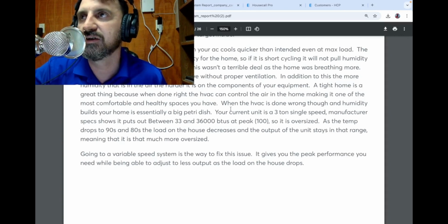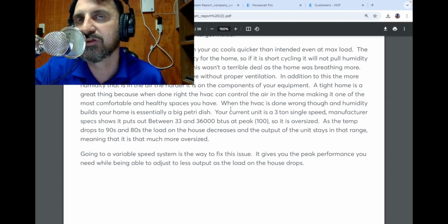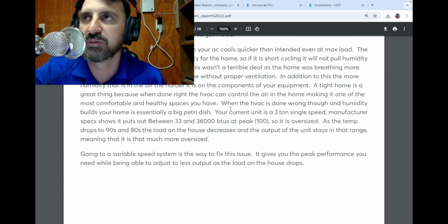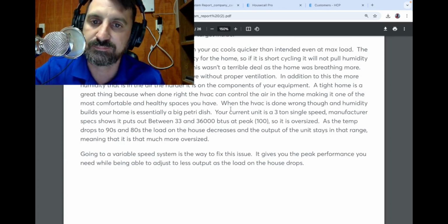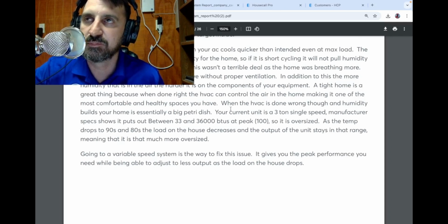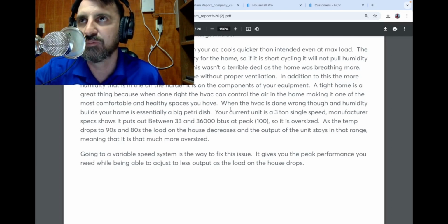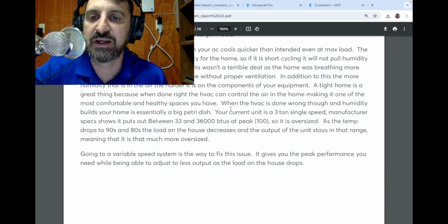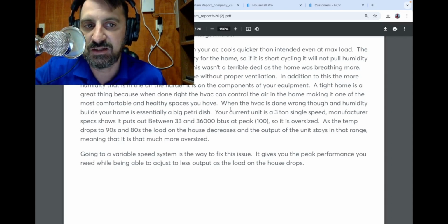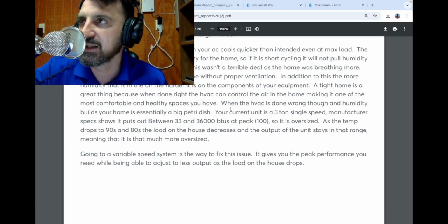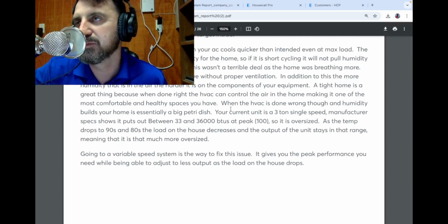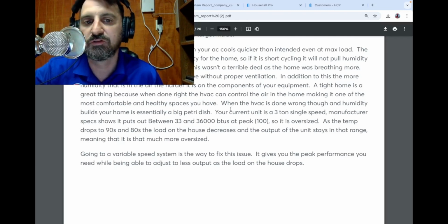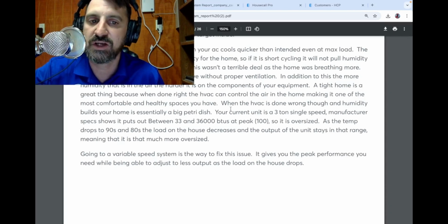It's going to turn on, it's going to cool the air so fast that the temperature drops, but the humidity is not pulled out. In a traditional home, you're passing air from inside and out. Moisture can travel from inside and out. It can kind of balance with the outside air. In a tight home, it's not the same thing. That humidity can't transfer in and out through the foam. So basically, you're sealing this home tight.